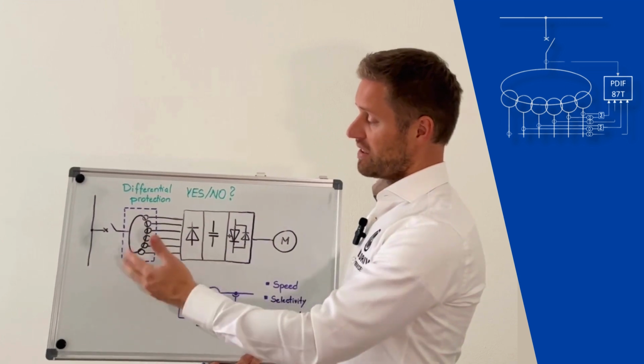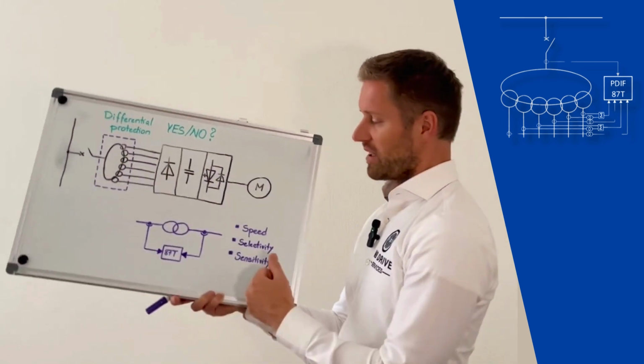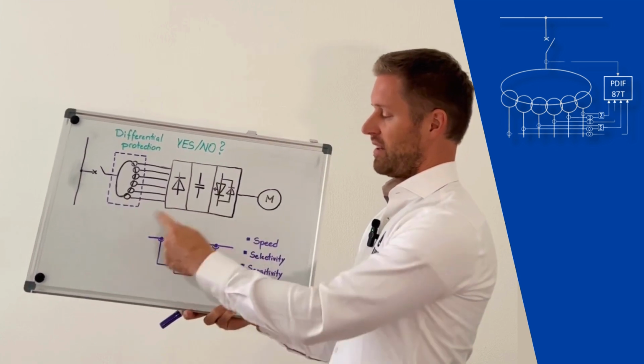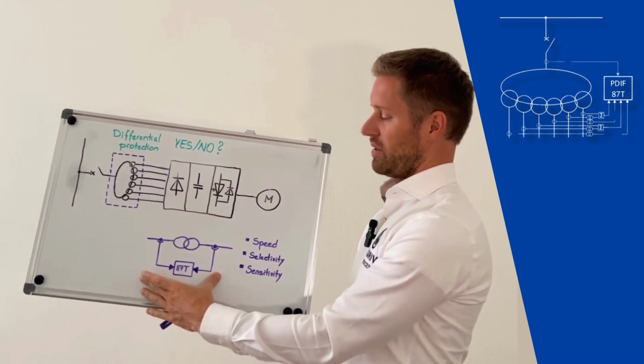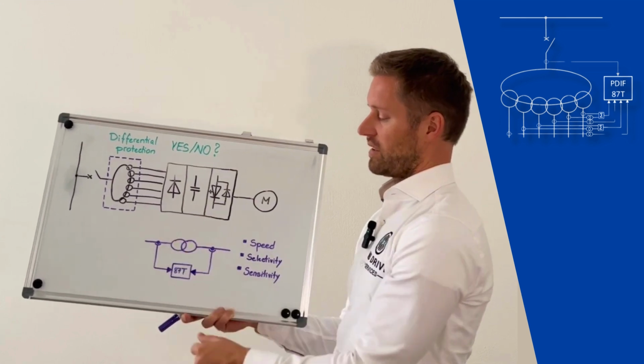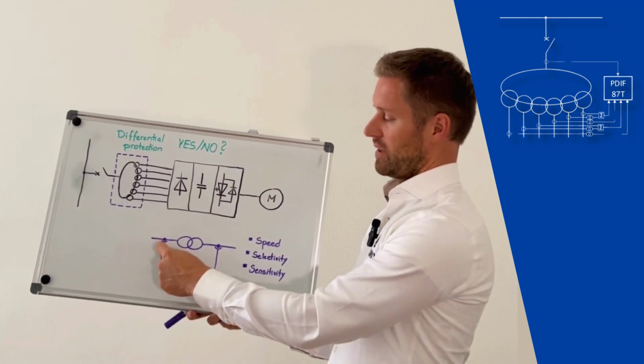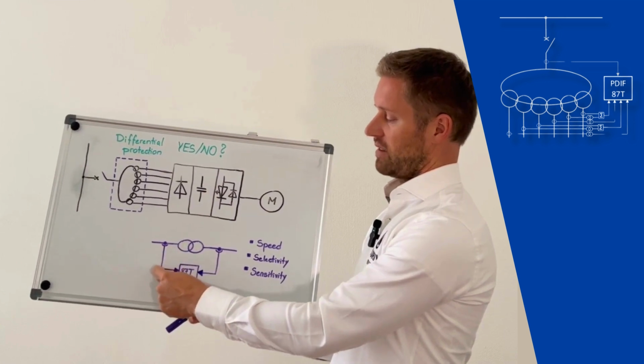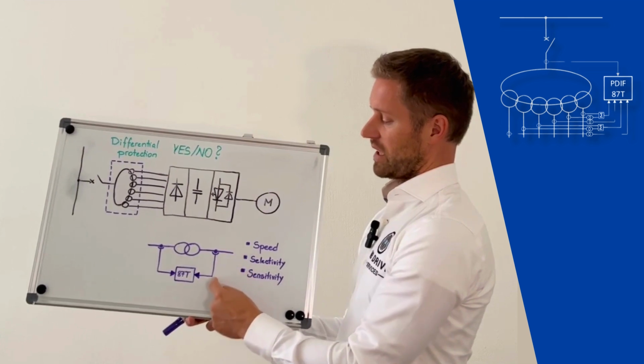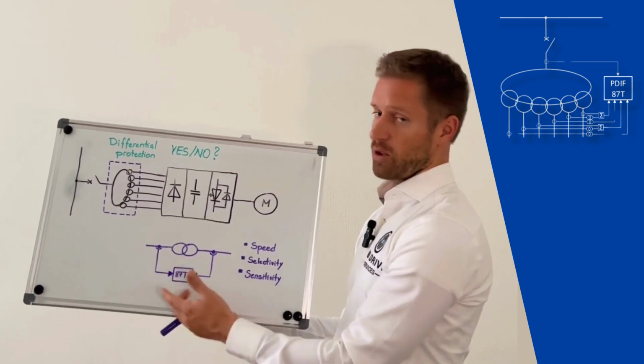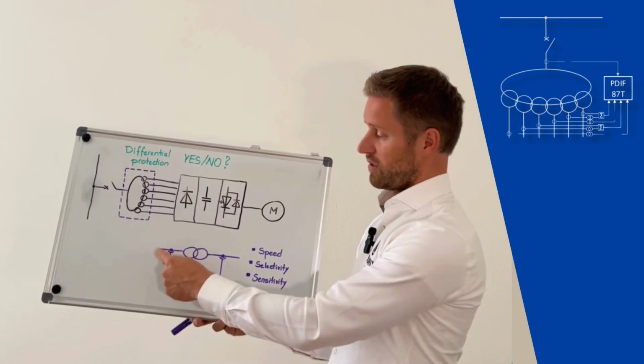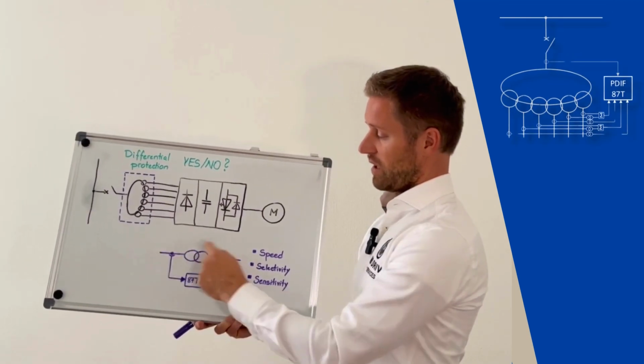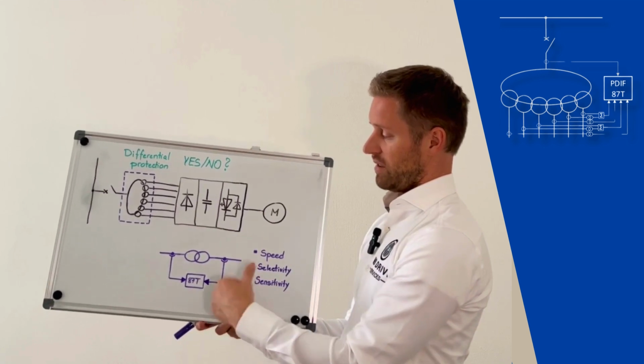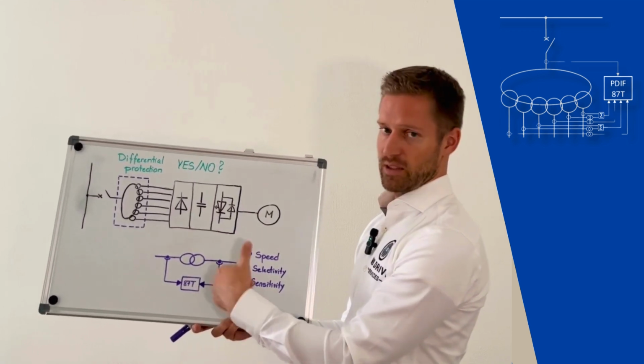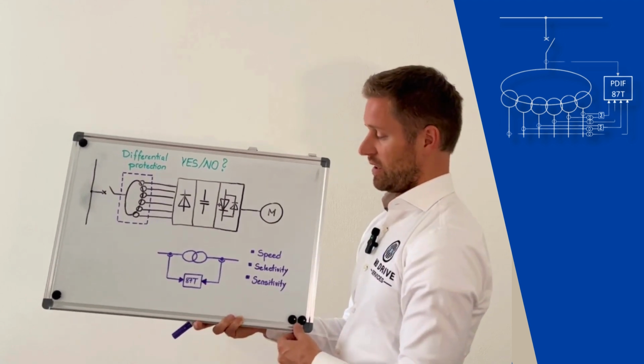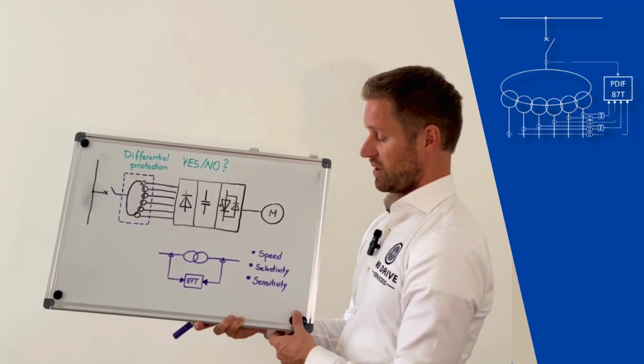Before going into the details and into the discussion, we take one step back. We look at the, let's say, simplest possible differential protection on a two-winding transformer. We have a current measurement on the primary side. There is also a current measurement on the secondary side, and the relay compares those two currents. Of course, the nominal current in amps on the primary and secondary side is different, but this is covered by the scaling of the CT or by referring to the percentage value of the nominal current.